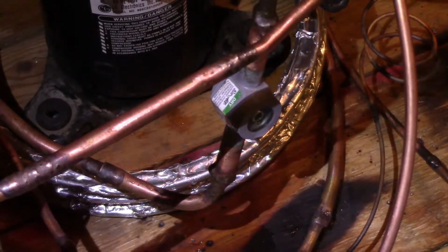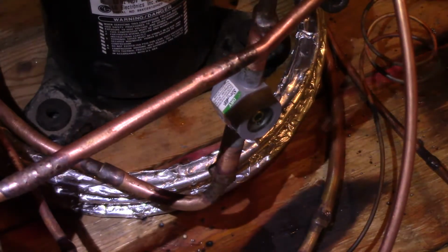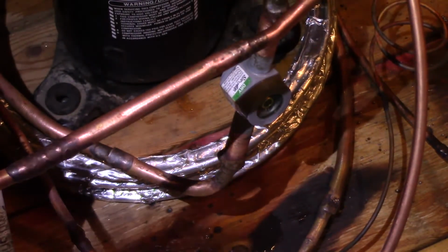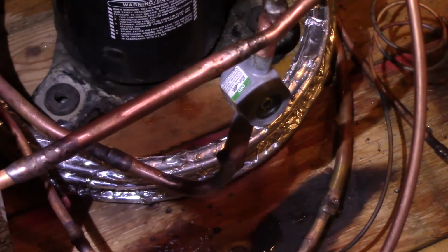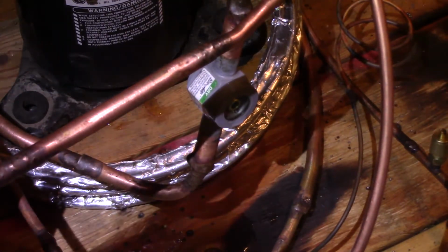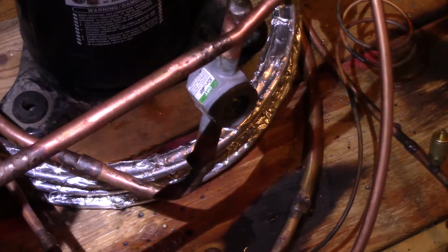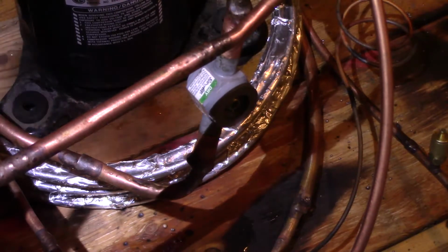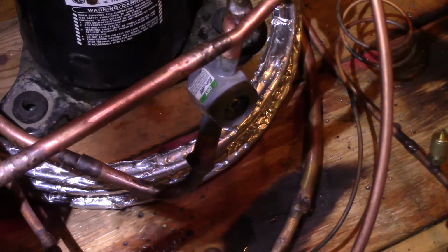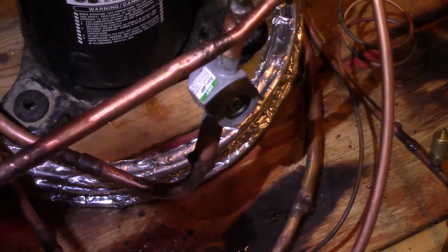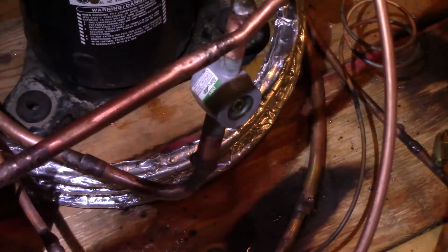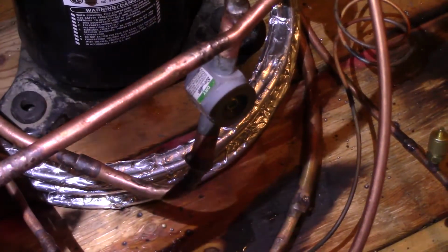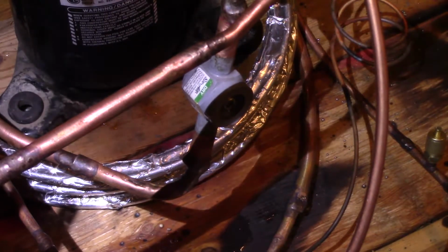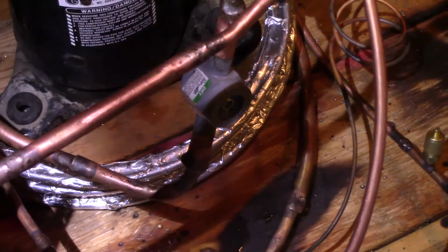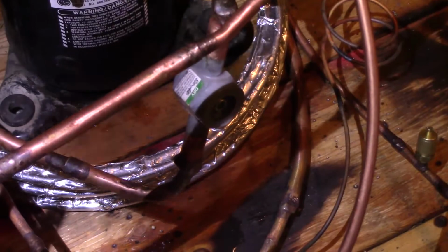The heat exchanger is there. What it is, the discharge of the low temperature cycle is a 1/4-inch tube, and it is soldered onto a 3/8 tube, and that forms a heat exchanger. So the 3/8 tube is going to be the evaporator for the high temperature cycle, and the 1/4-inch tube is going to be the condenser for the low temperature cycle. And unfortunately, it's actually very, very bad as a heat exchanger. There's quite a bit of temperature overlap, and I'll explain all that here in a minute.